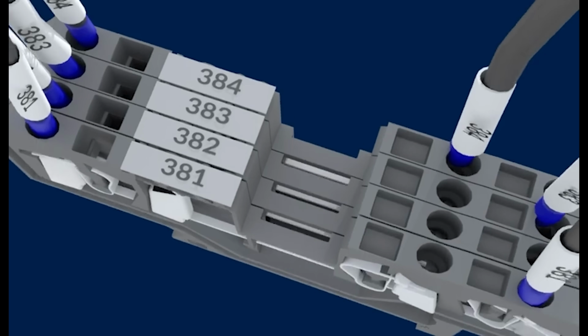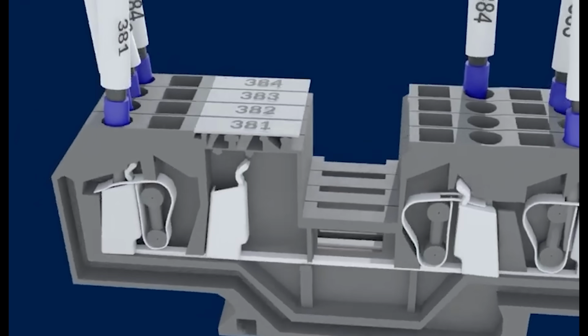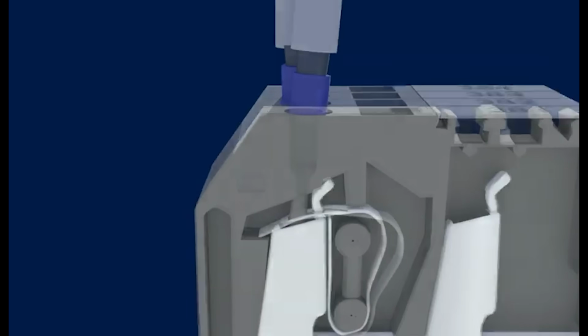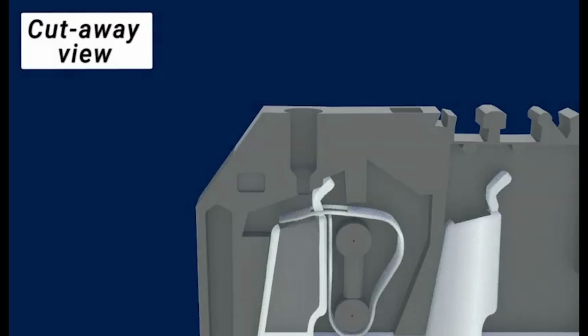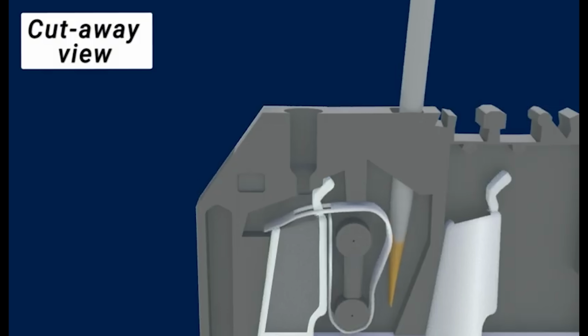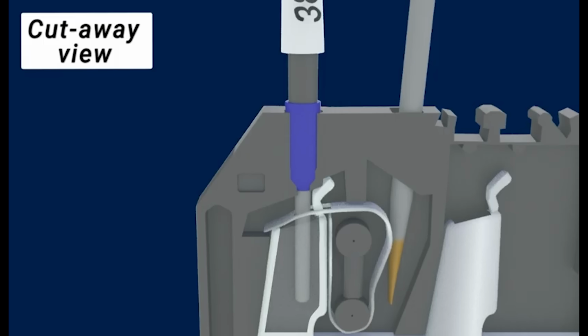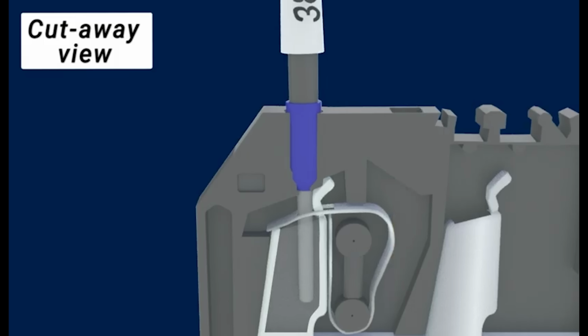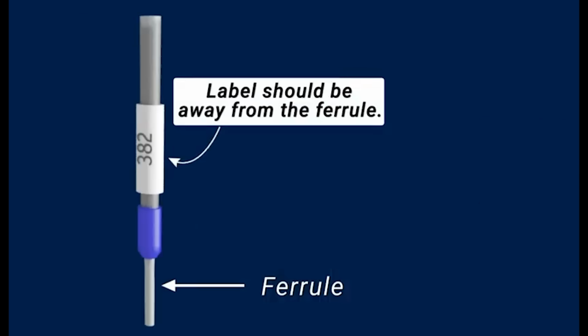Okay, so here you can see 4 terminal blocks on the DIN rail that have their wires connected in there. To assemble the wires into the terminal block, you have to use a tool inserted into a side port that opens the spring clamp, which allows the wire's ferrule to slide into place through that rectangular eye you see on the top of it. When you pull the tool back out, this closes the spring clamp, securing the ferrule firmly against the terminal block's internal conductor bar. Labeling bands identify the wires and are typically positioned on the wire insulation, as you can see further back.